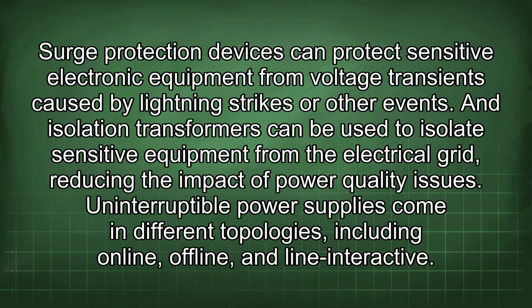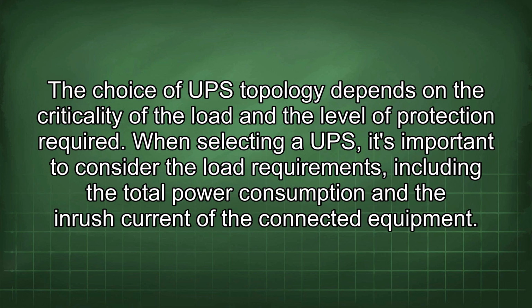Surge protection devices can protect sensitive electronic equipment from voltage transients caused by lightning strikes or other events. And isolation transformers can be used to isolate sensitive equipment from the electrical grid, reducing the impact of power quality issues. Uninterruptible power supplies come in different topologies, including online, offline, and line interactive. The choice of UPS topology depends on the criticality of the load and the level of protection required.